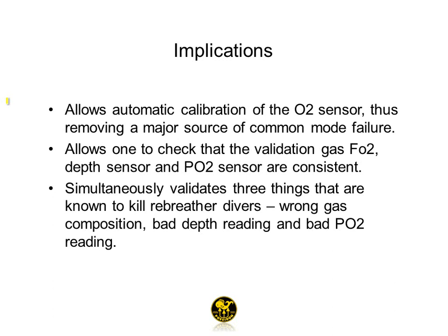Furthermore, because we're doing this in a highly controlled environment, there is no ability for the user to screw up the calibration. The bottom line is that it takes out what I consider to be the most important common mode failure across oxygen sensors. That is, using the wrong calibration gas.